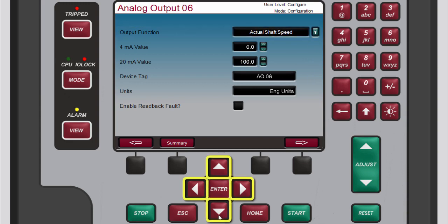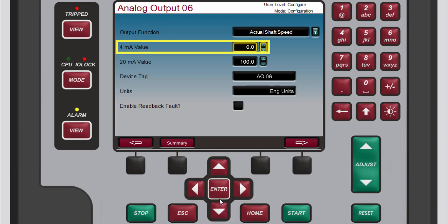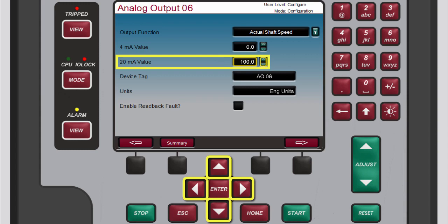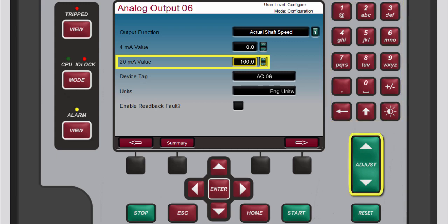Use the navigation cross keys to highlight the 4 milliamp value box, then press enter to select the current value. Use the numeric keypad to replace it with the desired value, and then press enter again to confirm the change. Use the navigation cross keys to highlight the 20 milliamp value box. To replace the current value, you can either use the numeric keypad like you did for the 4 milliamp value box, or you can use the adjust keys to reach the desired value. For this demonstration we will not change this value.